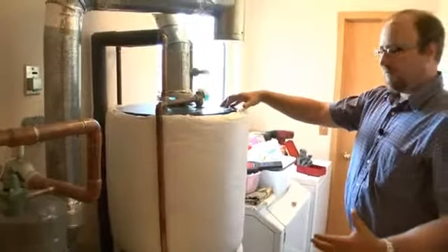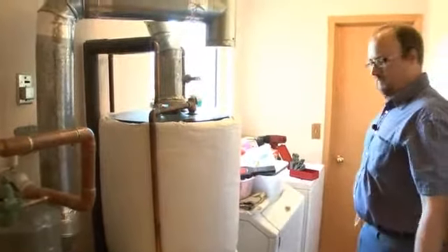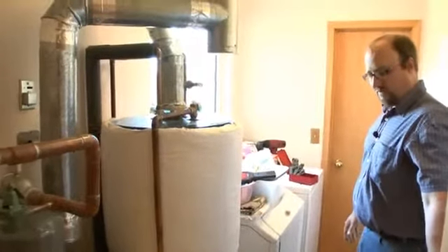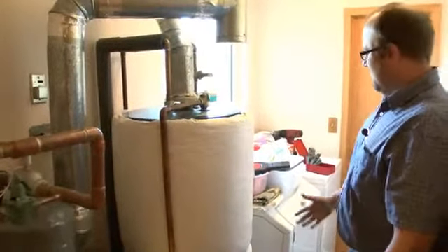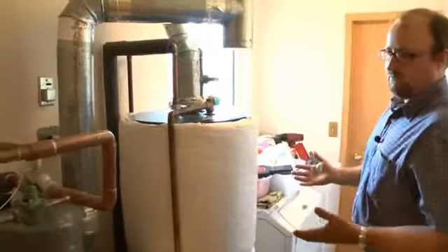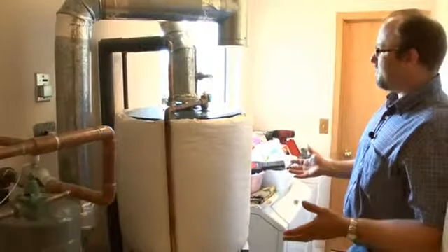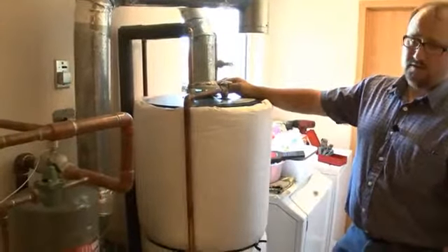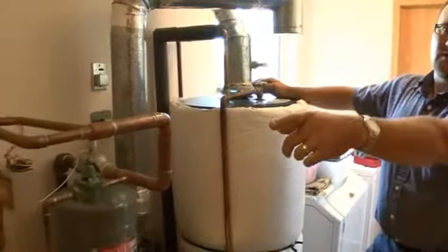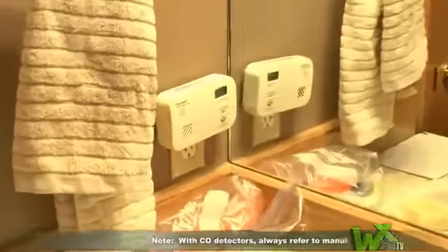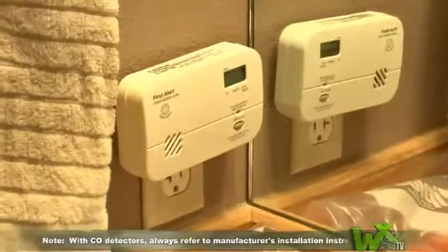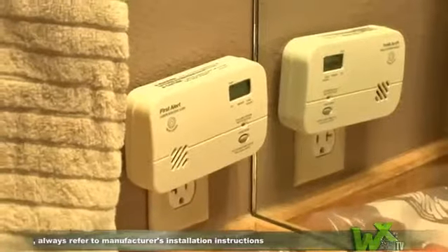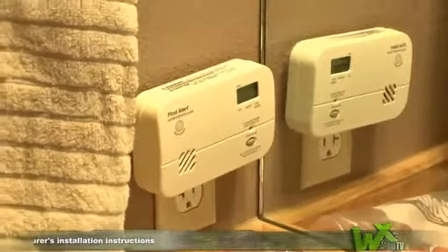The other thing about this room is it's a fairly small room. The door's probably shut quite often. With the door shut and the dryer running, there's a really good chance that we create a negative pressure in here. One good thing that I notice is that right over here in the room that's connecting is a carbon monoxide detector, which is a positive thing: if this does backdraft and there is CO, that unit would catch that.